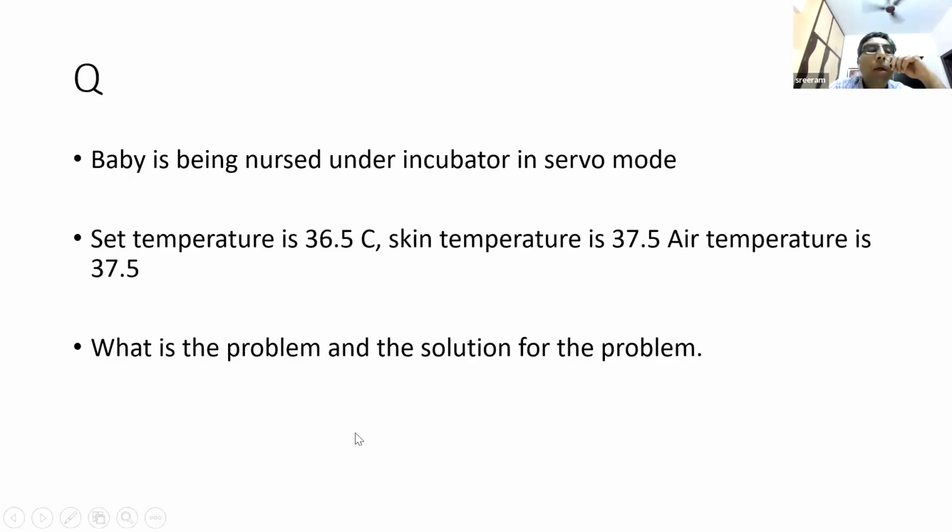Yeah. Baby is being nursed under the incubator in a servo mode. Set temperature is 36.5. Skin temperature is 37.5. Air temperature is 37.5. So where is the problem? Incubator mode. Set temperature is 36.5.